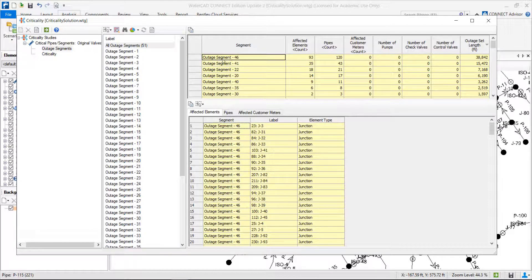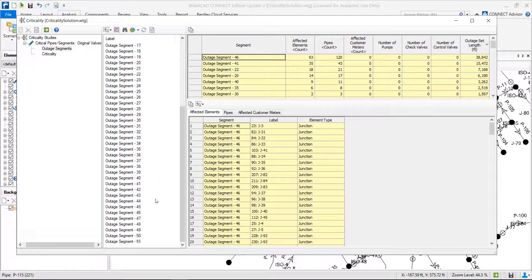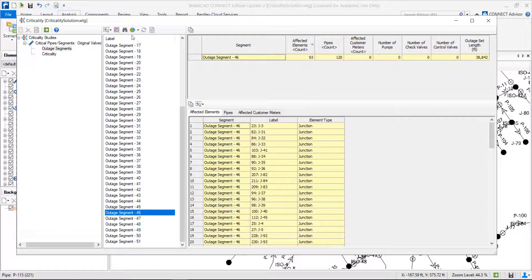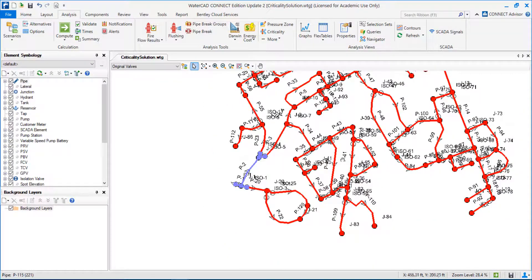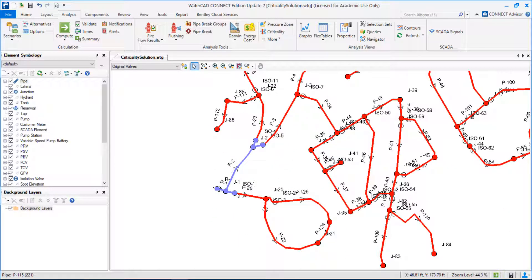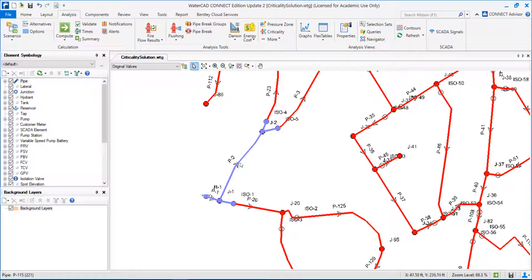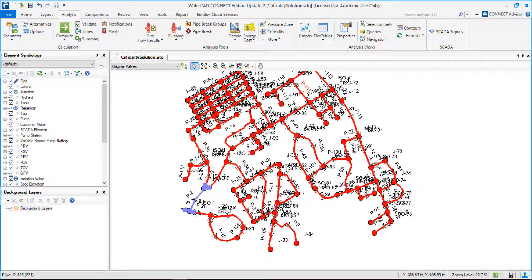Basically, this means that if we close segment 46, 38,000 feet downstream of this segment will be affected without water. Let's look at segment 46 — we select it and highlight in the map. Now I have an interesting view. The segment in purple represents the segment that I need to close if I have a burst here, and all the red pipes represent the pipes that will be affected, that will be without water.